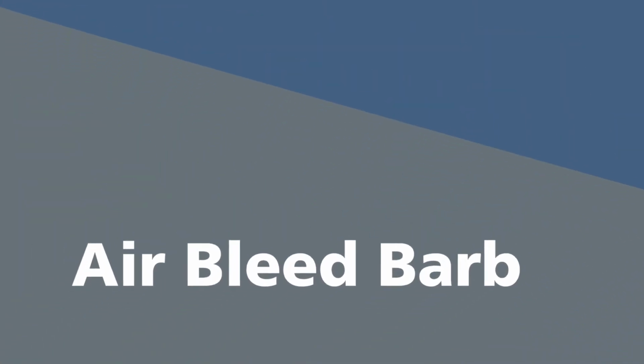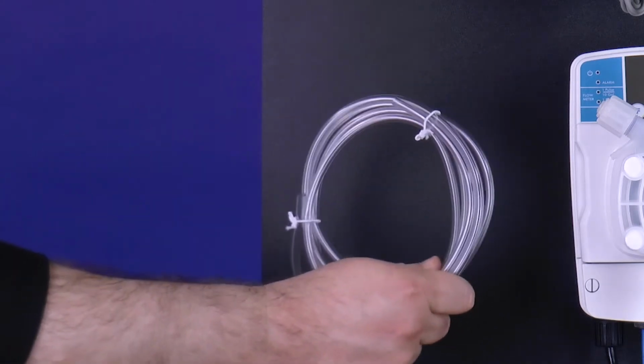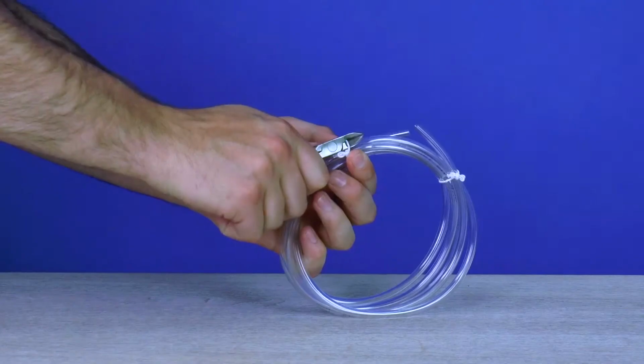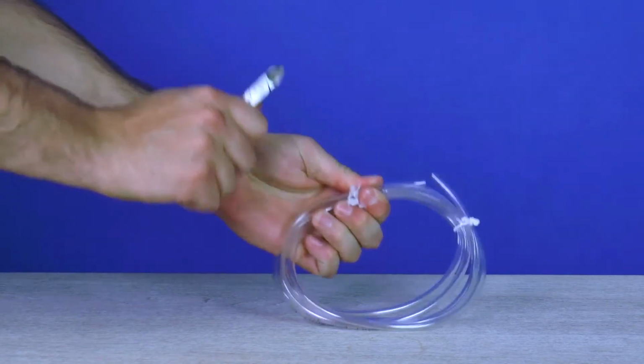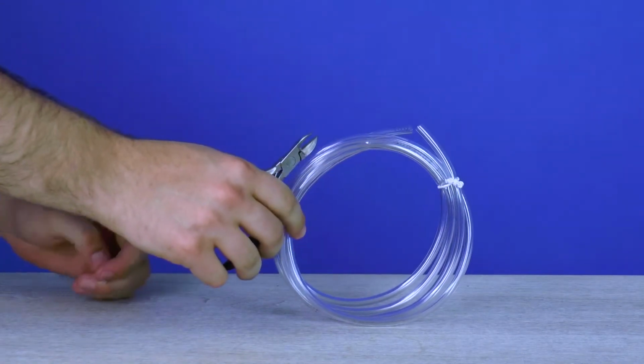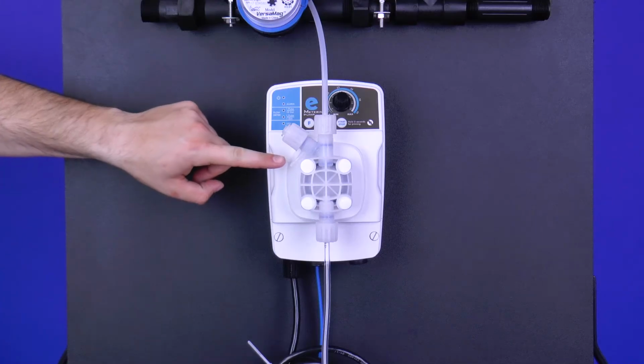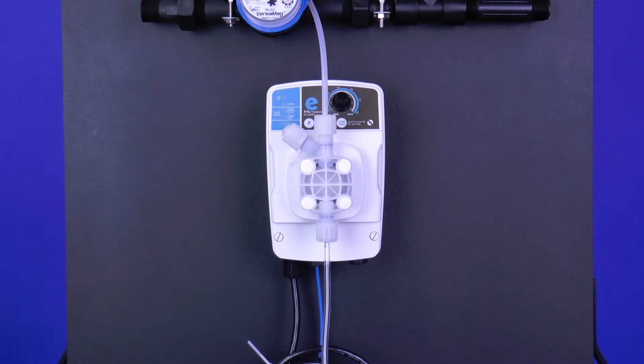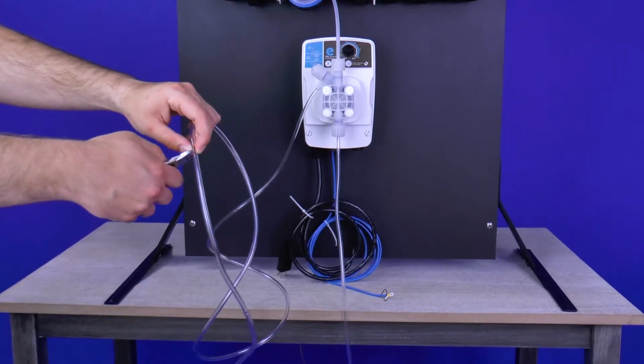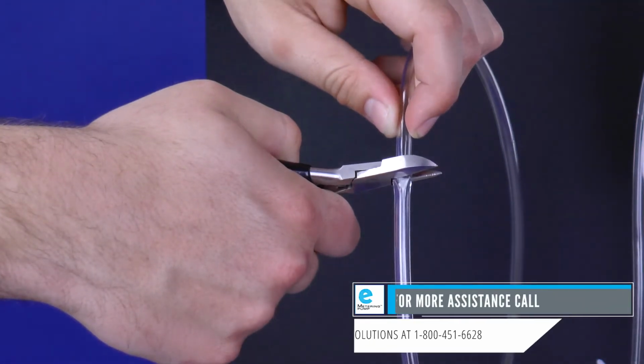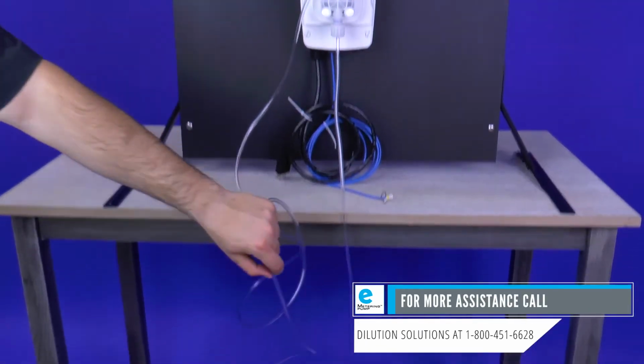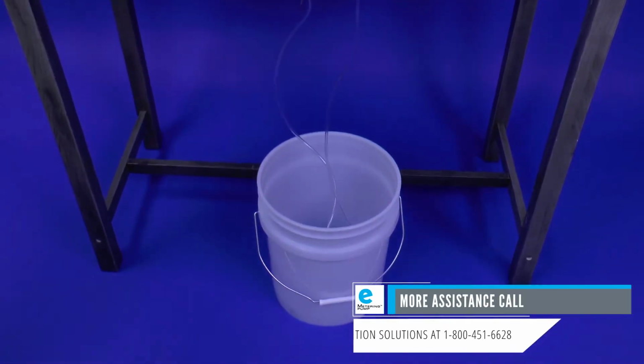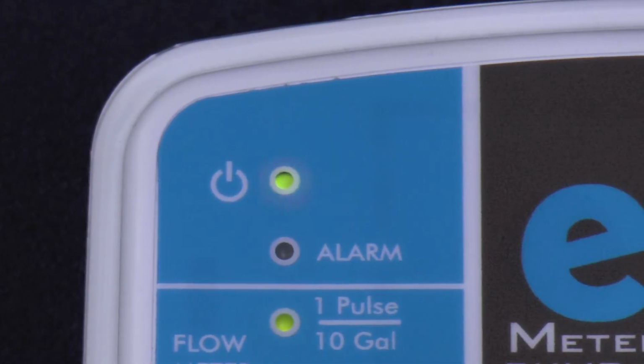Air bleed barb. Finally, take the smaller remaining PVC tubing out of the tubing kit. Using diagonal pliers, cut and remove the string holding the tubing together. Locate the manual air bleed barb on the upper left section of the pump head and slide one end of the PVC tubing over the barb. Using the diagonal pliers or cutters, cut the tube so that it is long enough for the chemical bleed off to go back into the bucket or stock tank while priming the eMP pump.